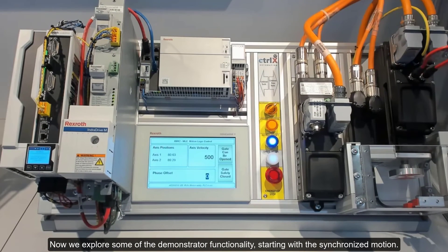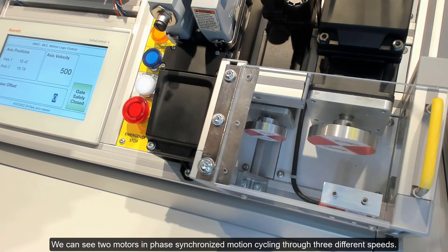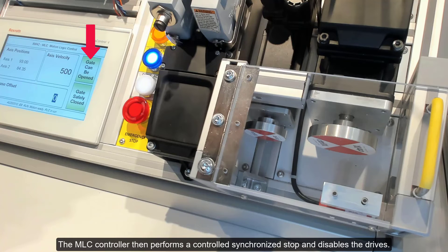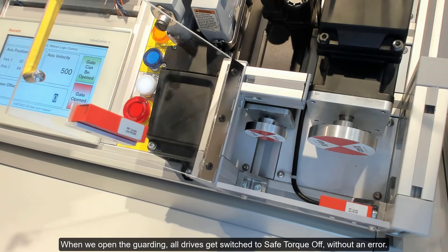Now we explore some of the demonstrator functionality, starting with synchronized motion. We can see two motors in phase synchronized motion cycling through three different speeds. To open the safety guarding without causing an error, we can press the access push button. The MLC controller then performs a controlled synchronized stop and disables the drives. When we open the guarding, all drives get switched to Safe Torque Off without an error.